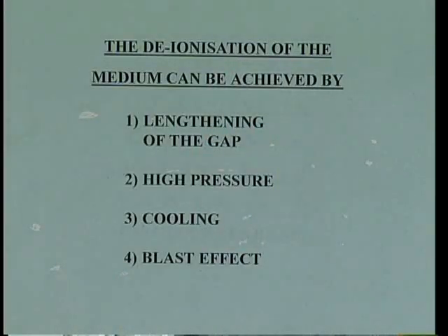And the last one is the blast effect. Here we replace the ionized particles with unionized particles, either by a gas blast or air blast along the arc, or by forcing oil across the arc. We can increase the dielectric strength of the medium.